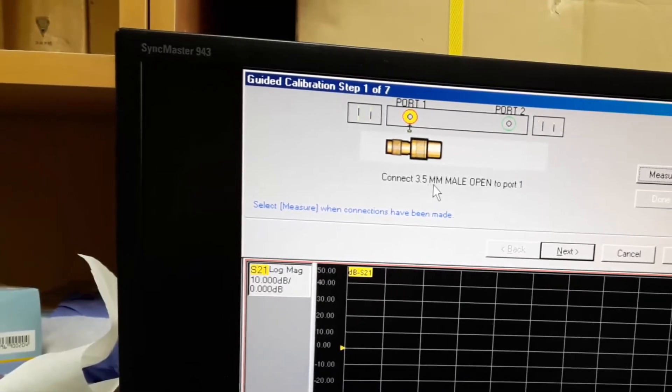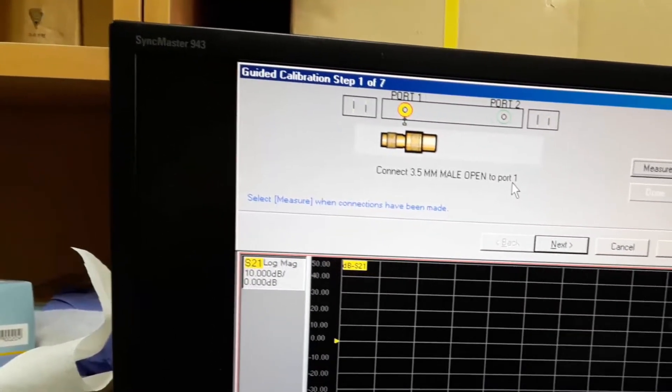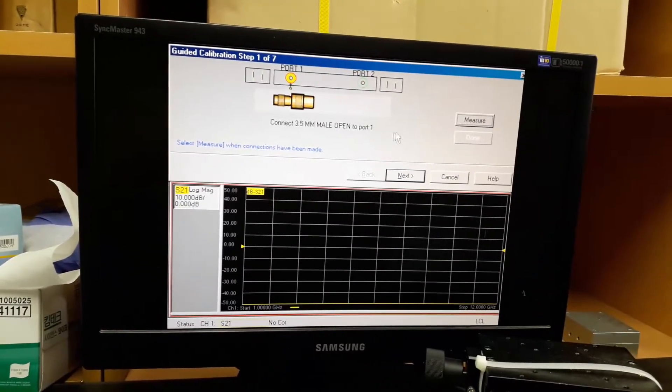Now it asks for the 3.5 mm MALE open standard to be connected to port 1. I have already connected the open standard to port 1, so just press measure.